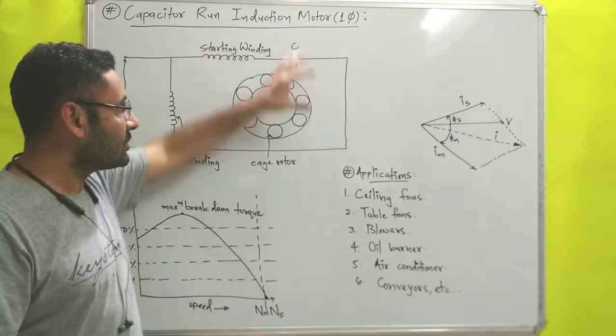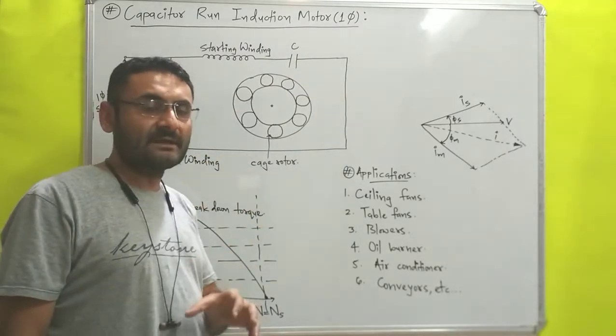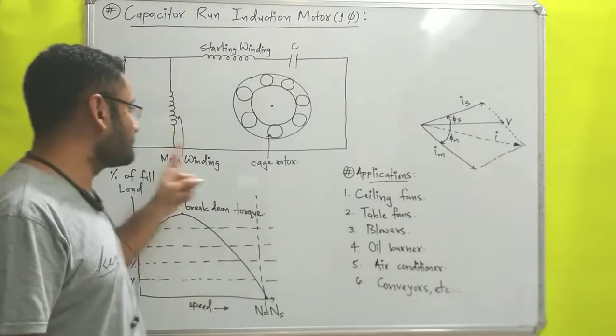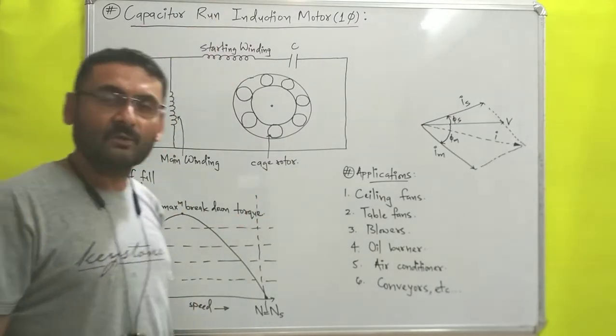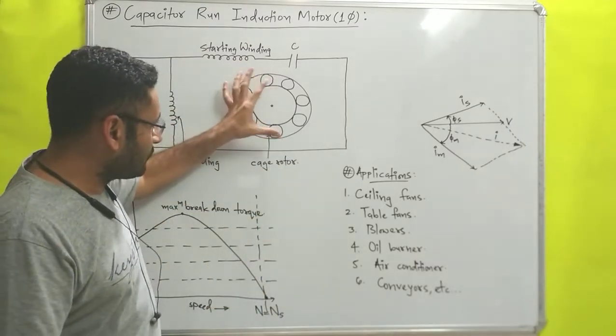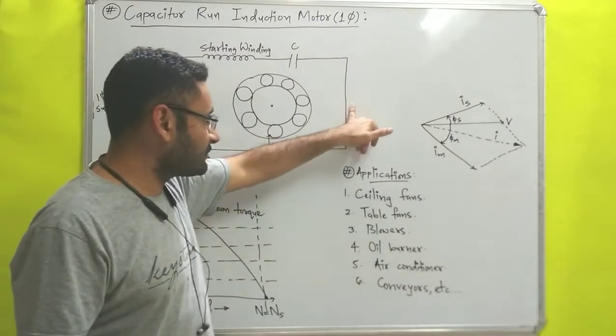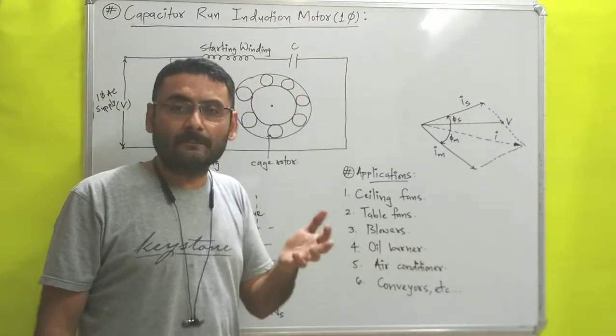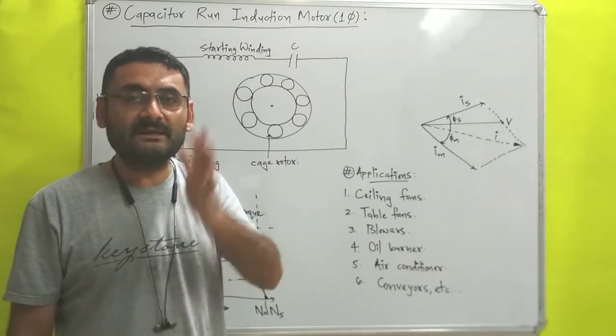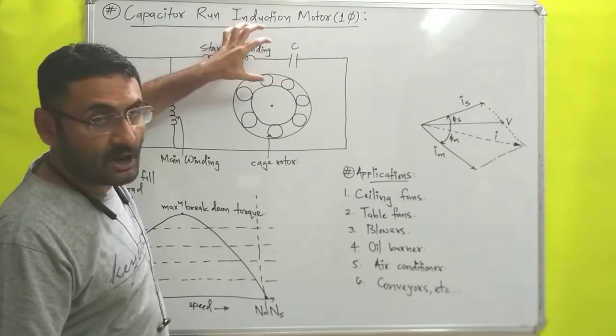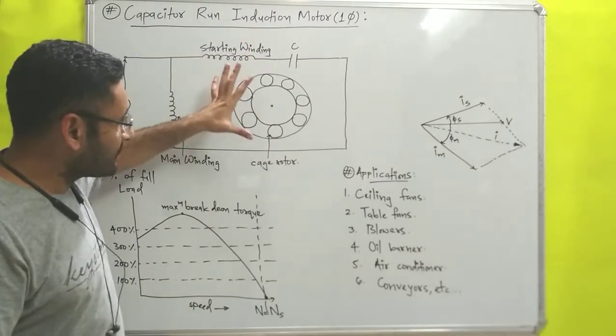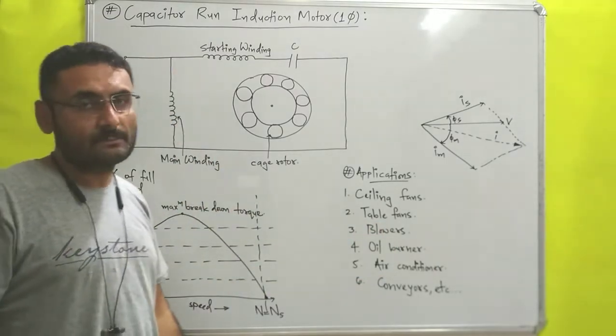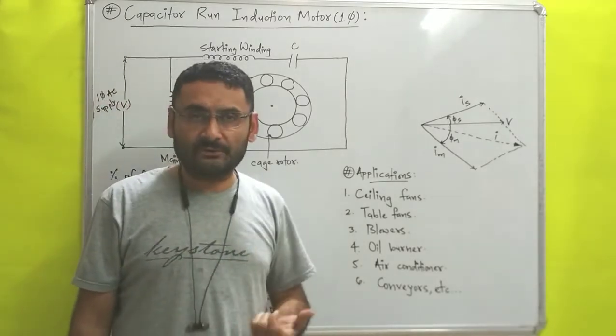A question may arise: how does that capacitor run the motor? The simple answer is that the capacitor will produce a phase difference between the two currents flowing from the main winding and the starting winding. Due to that phase difference, the rotor will start to rotate. Since a centrifugal switch is not used here, even when the rotor reaches 70% of its maximum speed, the starting winding will not be separated from the main circuit. With the help of the capacitor, the rotor will keep continuing its rotation — that is why it is known as a capacitor run induction motor.